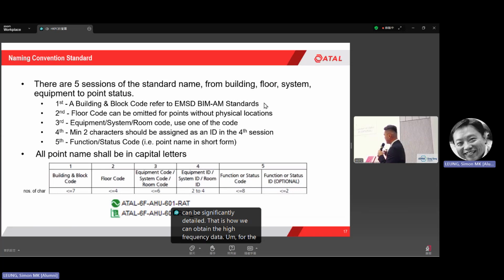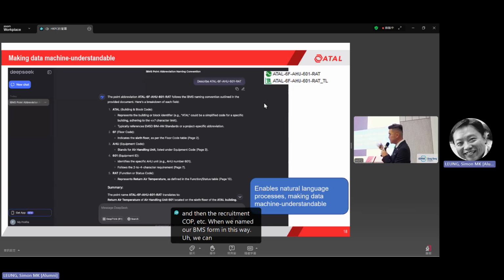For the naming of the BMS points, we actually have different standards. We use this standard to name our BMS points at our tower, starting from the building code, floor code, and then the equipment code, etc. When we name our BMS points in this way, the DeepSeek can understand the data meaning completely. That means for the RAT, the DeepSeek can understand this is the return air temperature. So by standardizing the naming of BMS points, it enables natural language processing and makes the data machine understandable.